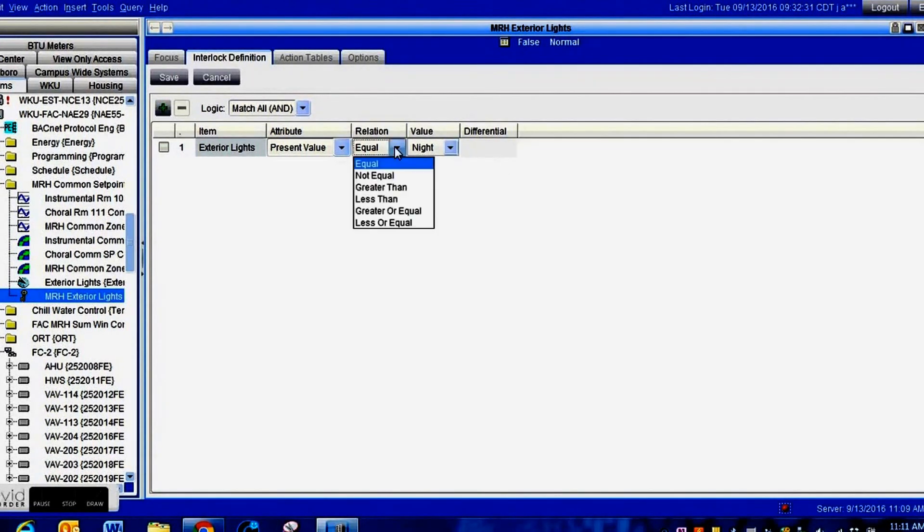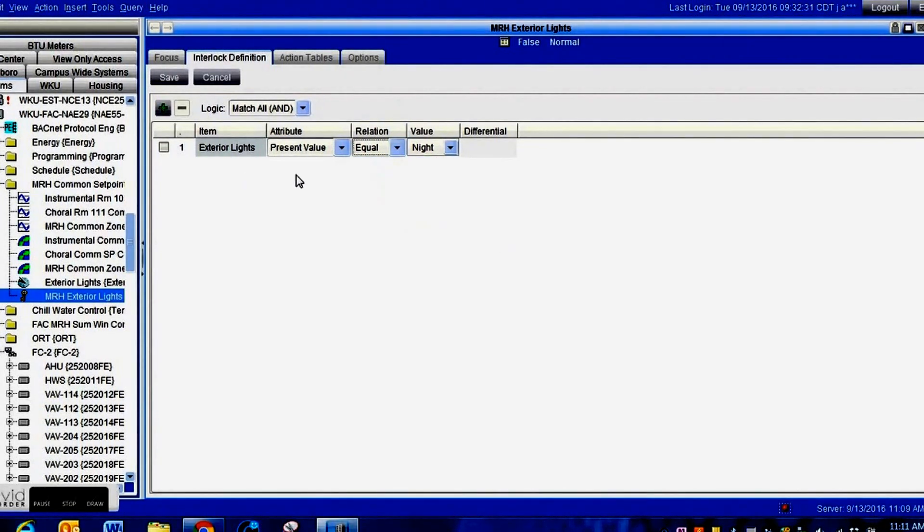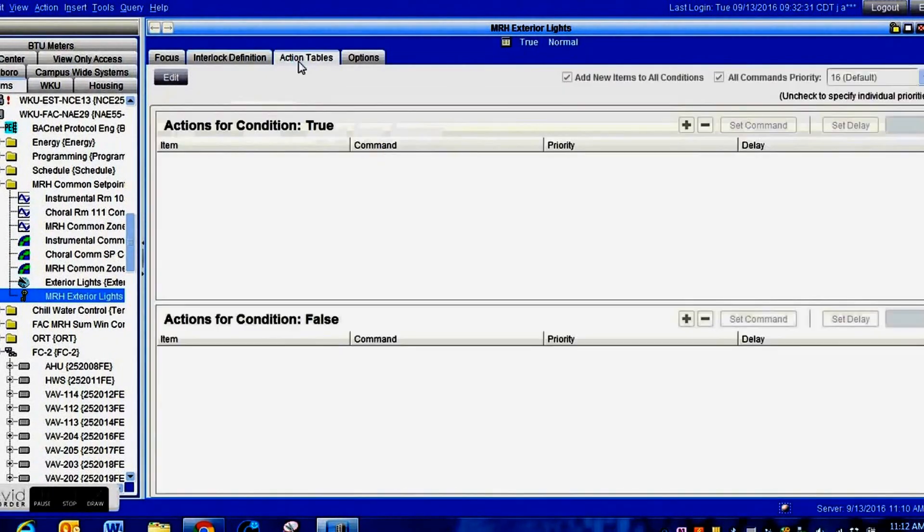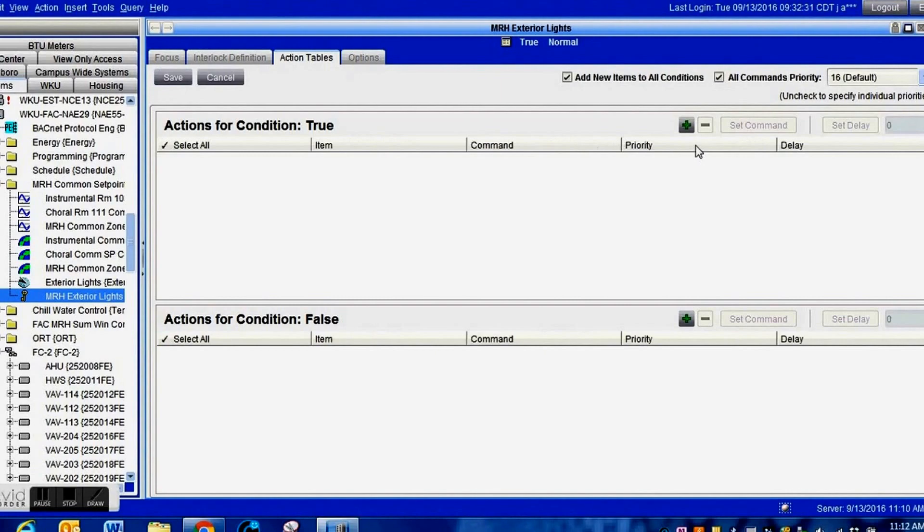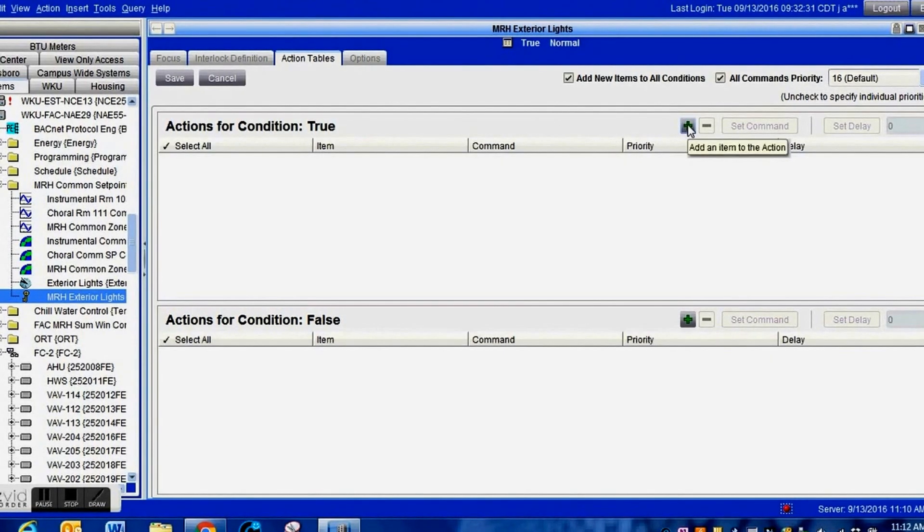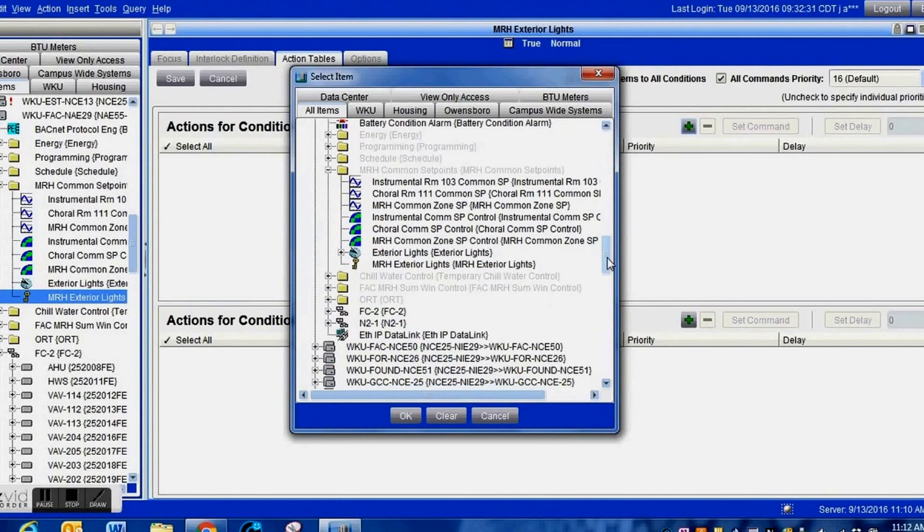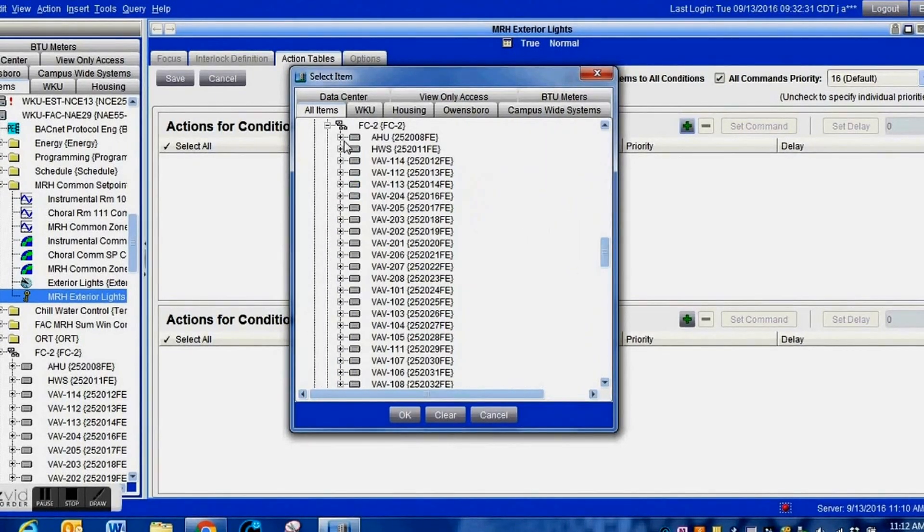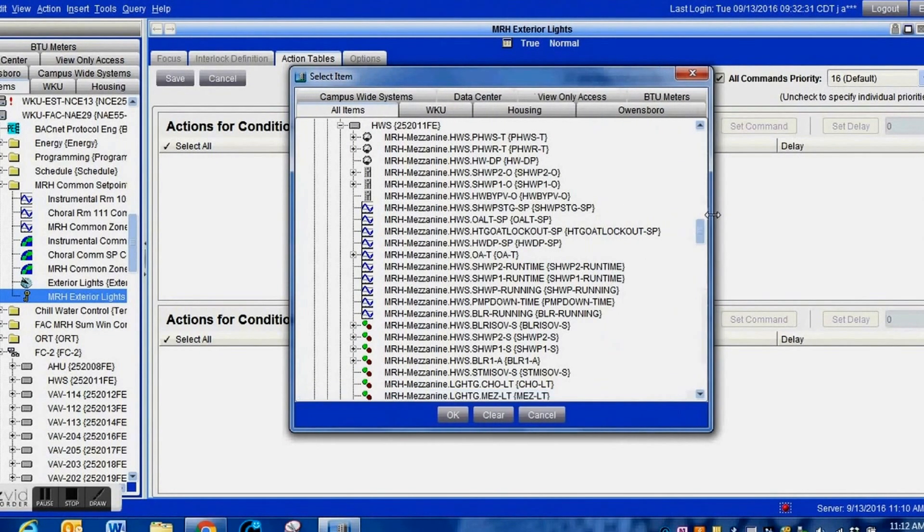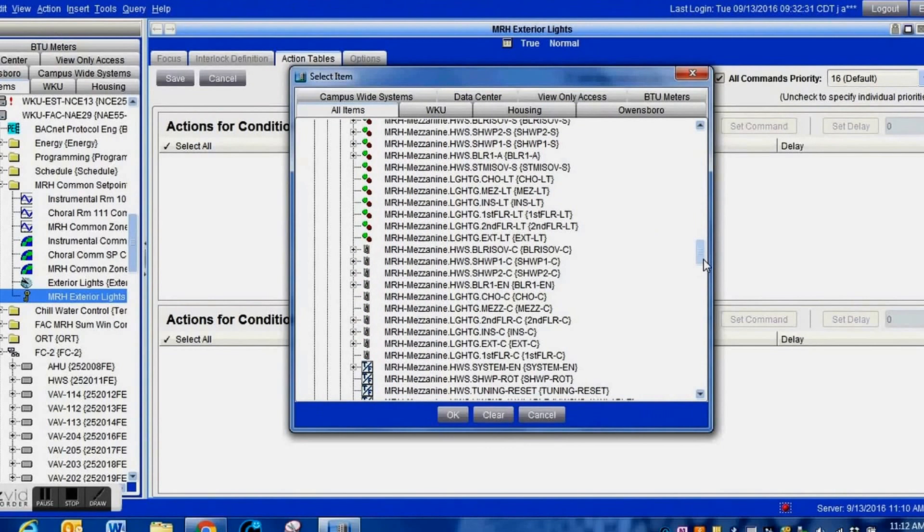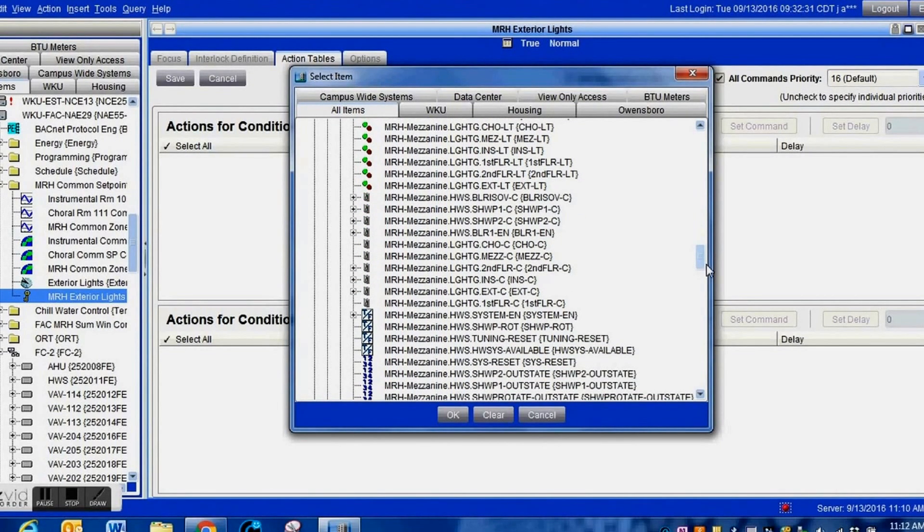It's going to give us our options here. You can reverse this if you need to. This is going to be exactly where we need it to be. If you wanted these to turn on something during the day, like a fountain pump or some type of display, it's just however you decide to use it. Right now we're going to leave this on night. If the solar clock says that it is night, the interlock will go true and then do whatever we put in here. We are going to add the command for our exterior lights.